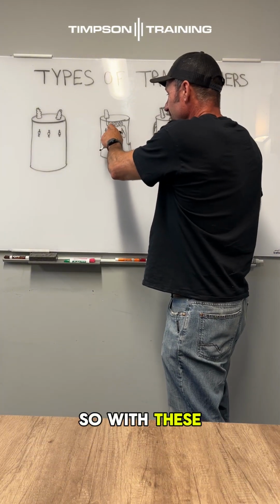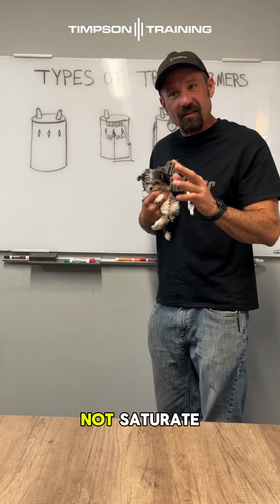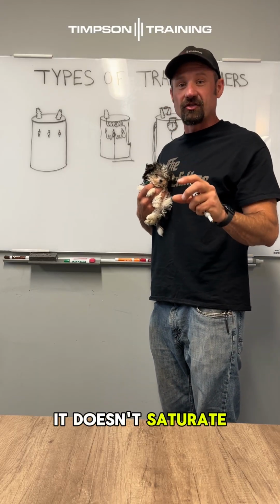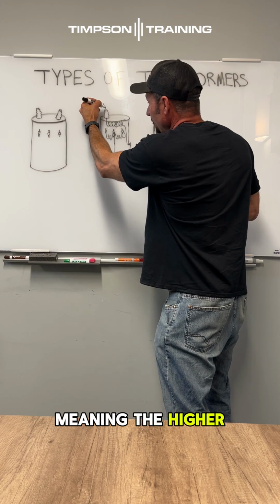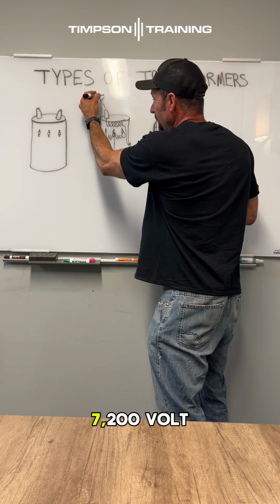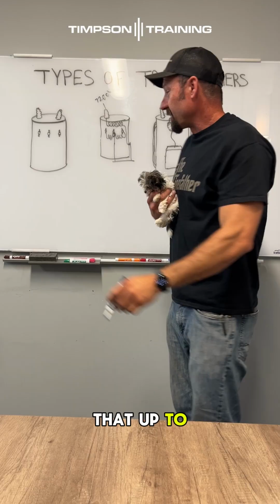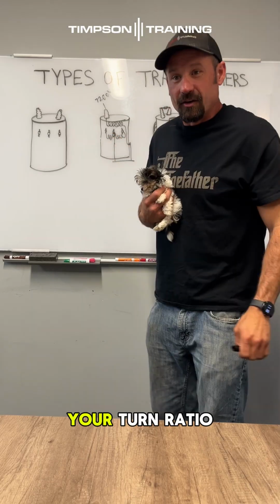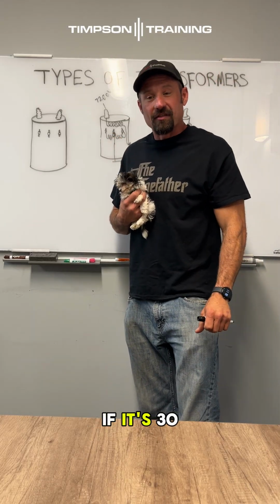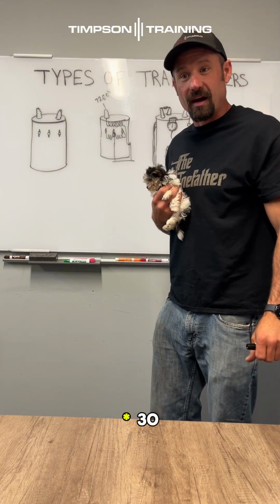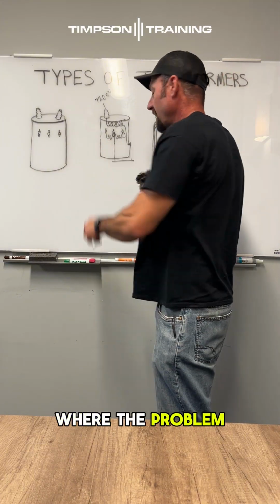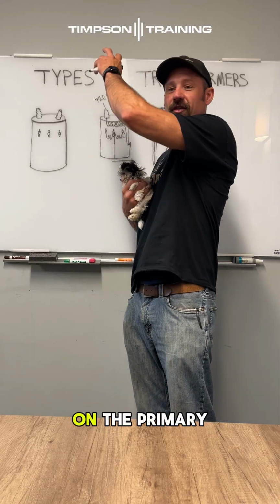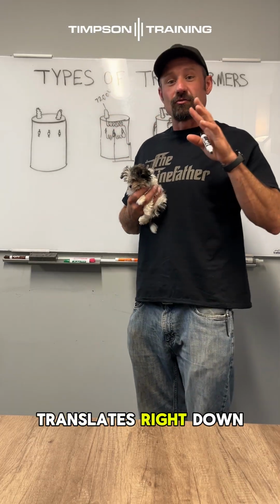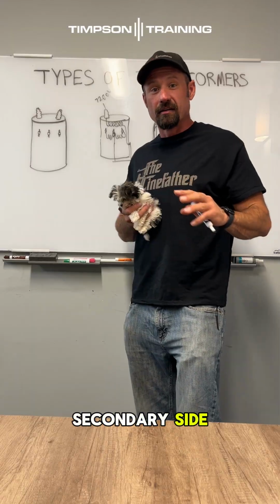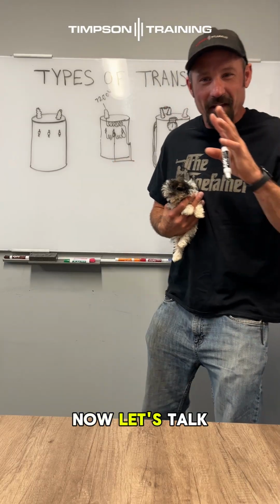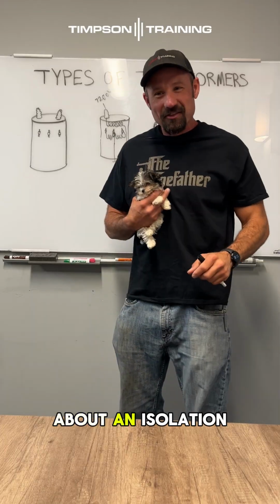So with these, the core does not saturate. It doesn't saturate very easy at all, meaning the higher I step this voltage up, say if this is 7200 volts and I step that up to 10,000 volts, well, your turn ratio remains the same. If it's 30-1, 10,000 times 30, you can see where the problem lies. That power surge on the primary side translates right down through to the secondary side. Vice versa. Now, let's talk about an isolation transformer.